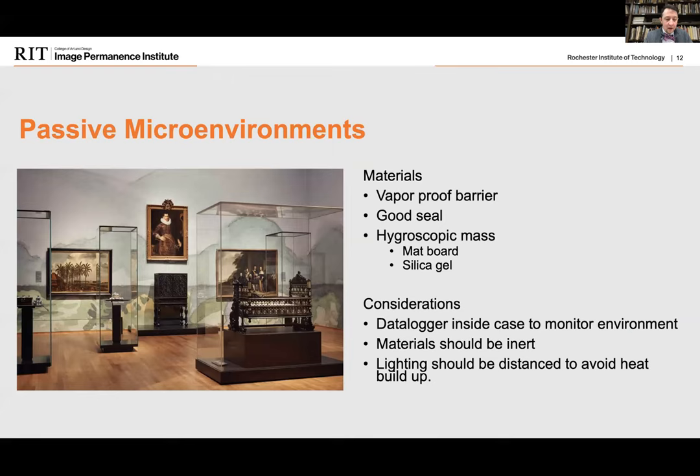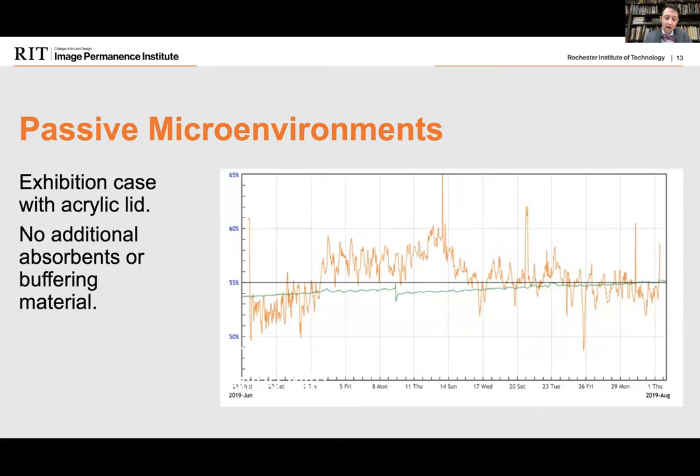With the mechanical approach, the institution saved $13,420 a year and had energy savings of 60,573 kilowatt-hours per year compared to what it would have taken to condition the entire gallery. The other option is the passive approach — a passive approach microenvironment should have a good vapor barrier and a good seal, and may or may not need additional hygroscopic material like silica gel. Other considerations include putting a data logger inside to monitor it, ensuring all materials are inert, and distancing lighting from the case to avoid heat buildup.